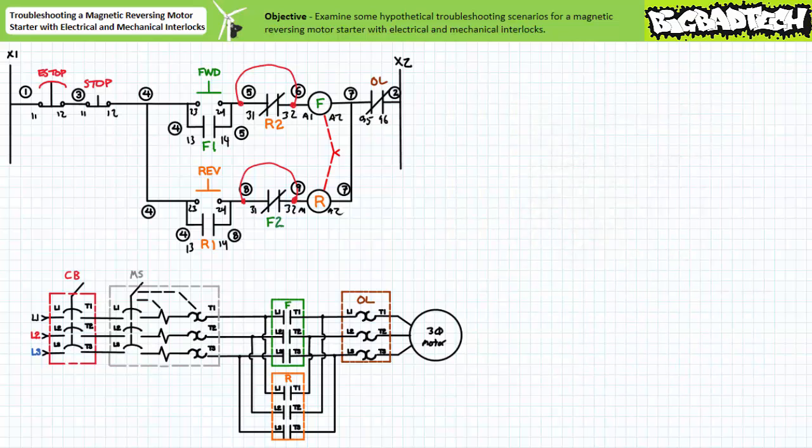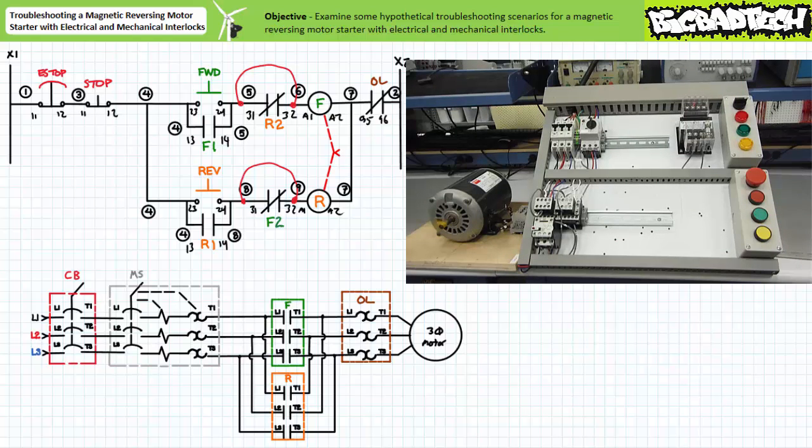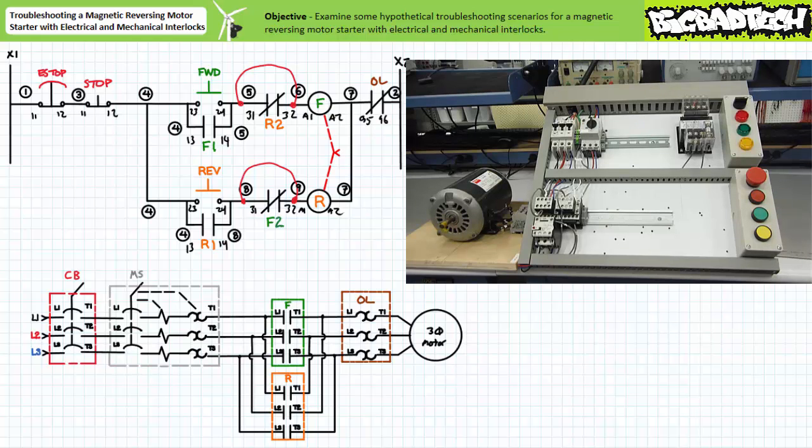When the system is placed in forward mode, the forward contactor closes as expected. Note, however, when I press reverse, the reversing contactor coil is energized because no electrical interlock prevents this from happening. However, the mechanical interlock prevents the reversing contactor carrier from moving. This sound is a dead giveaway that something stupid is about to go down and the mechanical interlock is doing its best to keep it from happening.